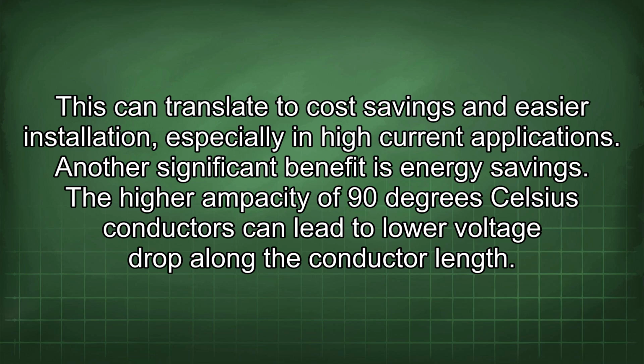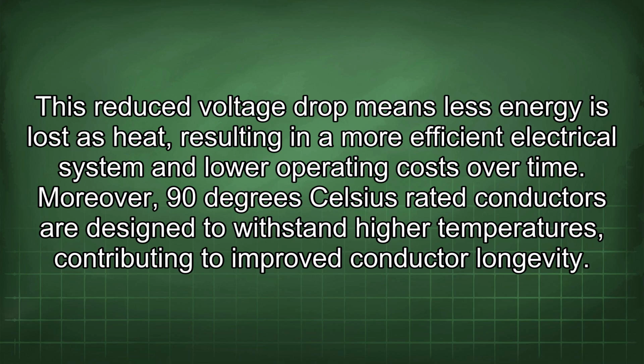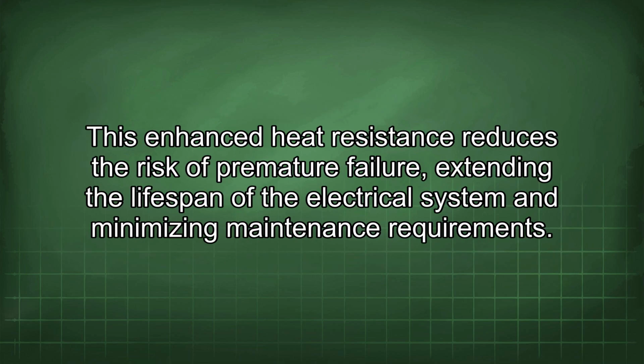Another significant benefit is energy savings. The higher ampacity of 90 degrees Celsius conductors can lead to lower voltage drop along the conductor length. This reduced voltage drop means less energy is lost as heat, resulting in a more efficient electrical system and lower operating costs over time. Moreover, 90 degrees Celsius rated conductors are designed to withstand higher temperatures, contributing to improved conductor longevity.